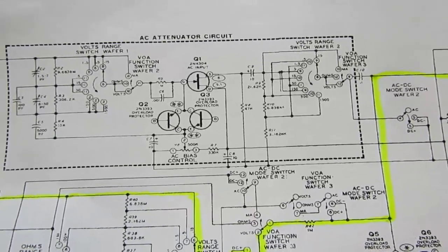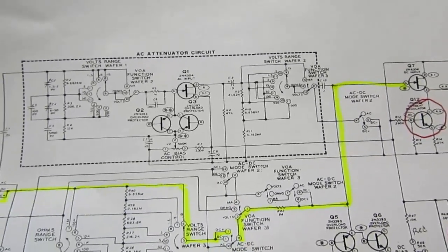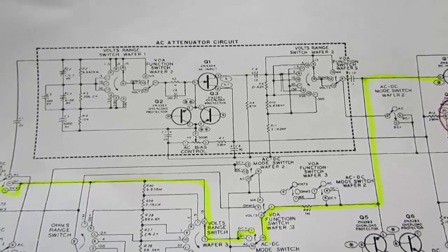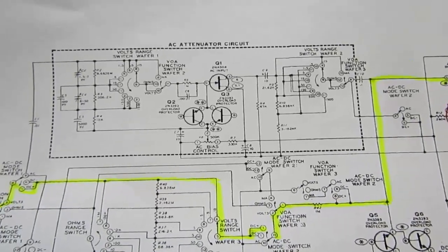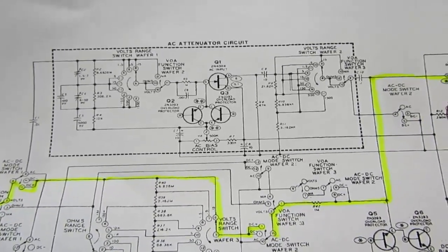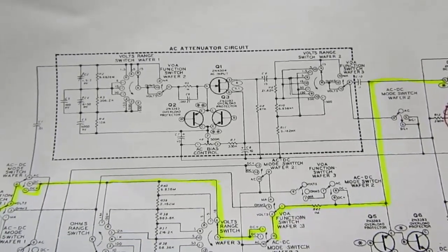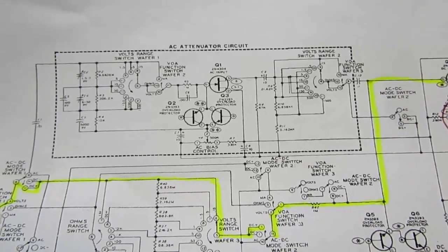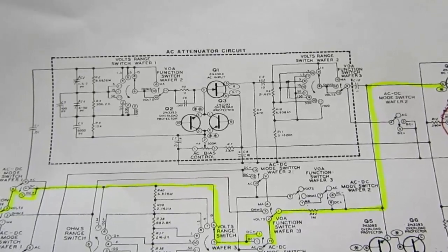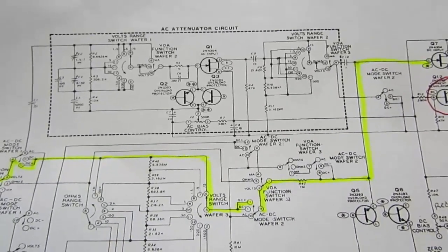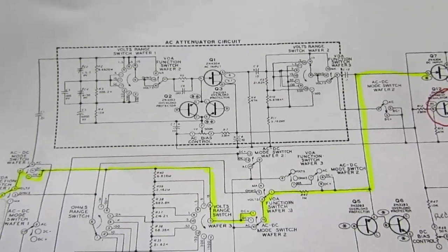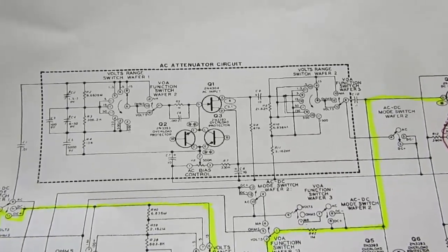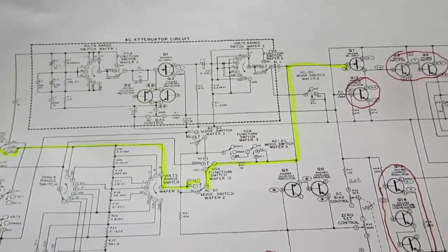And usually it'll be pretty close, but when I turn around and resell it, I just say, because of the inaccessibility of this one part that has failed or partially failed, the AC voltage function on the meter is no longer meeting its specifications, even though it gets pretty close, and could still be useful if you're just not looking for very high precision in the reading.